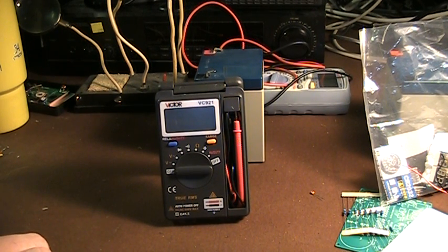If you plan to buy one of these meters, there is something that you should very definitely be aware of. There are two very different meters that are sold under this exact model number, general style of design, and brand name. Only one of them is the true RMS type. This is important for not one, but two reasons.